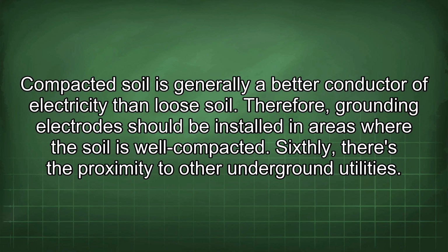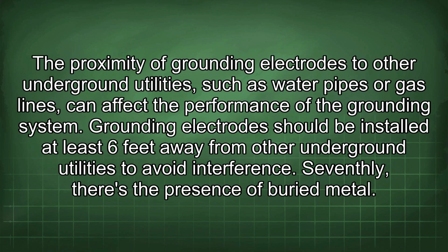Sixthly, there's the proximity to other underground utilities. The proximity of grounding electrodes to other underground utilities, such as water pipes or gas lines, can affect the performance of the grounding system. Grounding electrodes should be installed at least 6 feet away from other underground utilities to avoid interference.